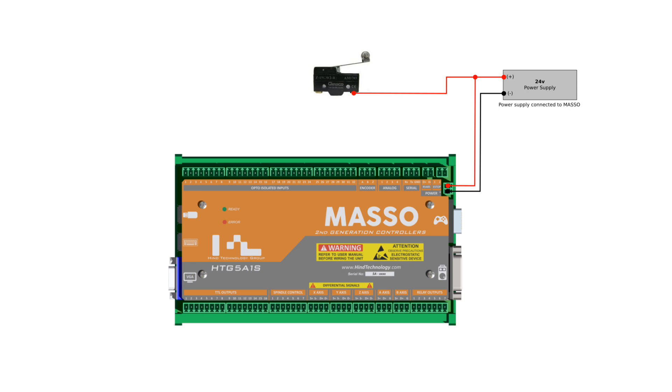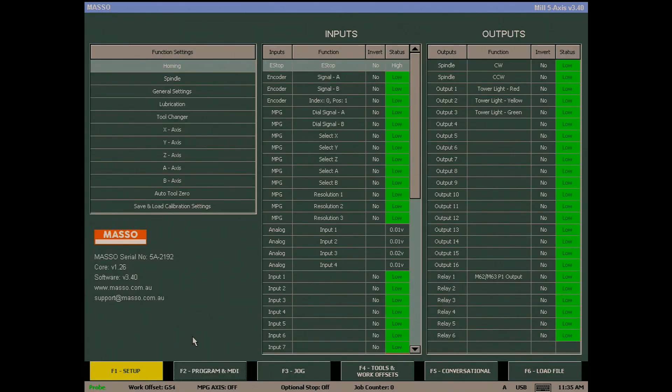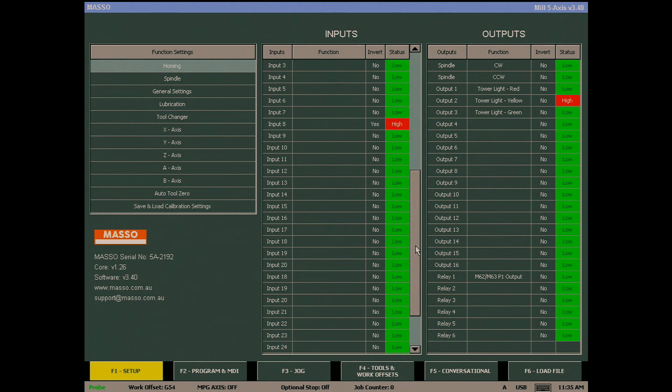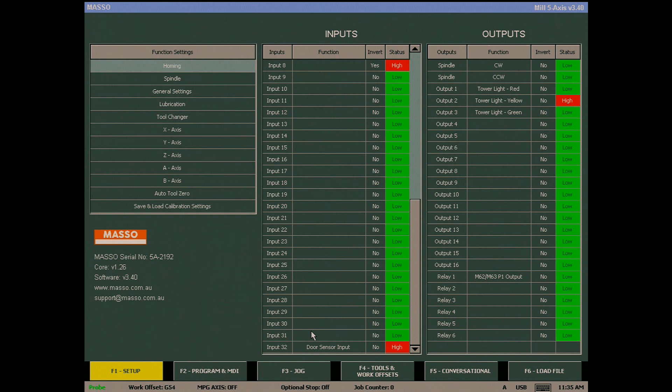On the F1 screen, the door sensor input should show High when the door is open and Low when the door is closed. In my case it is reversed, so I select the input and press the spacebar to toggle the status. Now when I open the door the input goes High and returns to Low when I close it again.